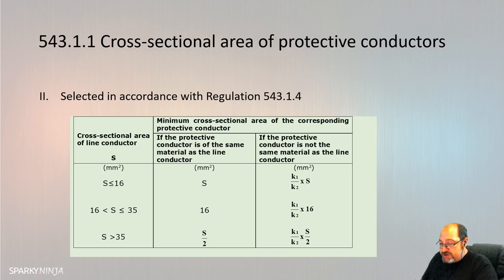When the protective conductor is formed by metal conduit, trunking or ducting, or the metal sheath of an armoured cable, the earthing terminal of each accessory shall be connected by a separate protective conductor to an earthing terminal incorporated in the associated box or other enclosure. This is the regulation that answers that question of, do you have to earth the back box or not?